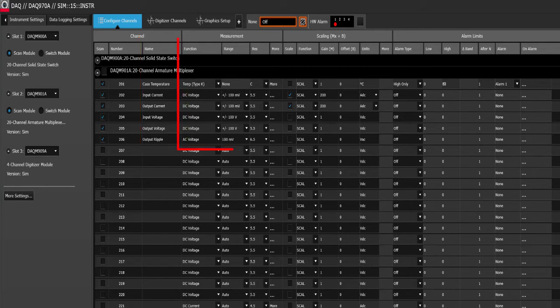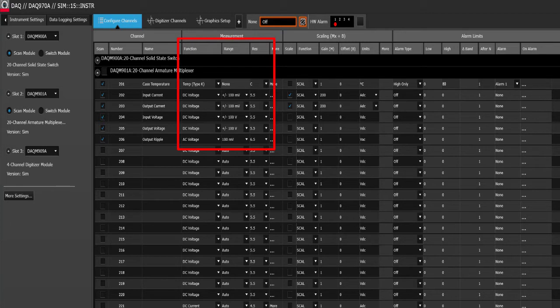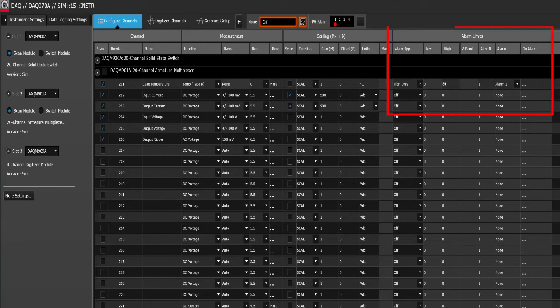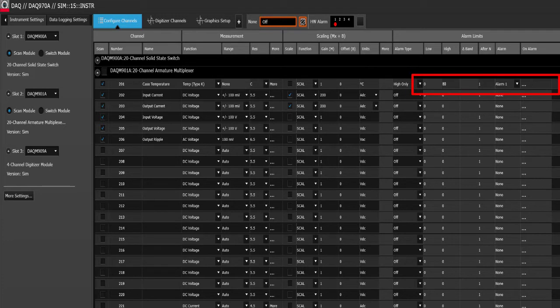We can also select the function, the range and the resolution and apply scaling factor and alarms if needed. In this case, we are using an alarm on the case temperature. If the temperature gets above 80 degrees Celsius, it will generate an alarm. We can choose from several types of alarms such as an email or a computer beep or a dot on the graph.